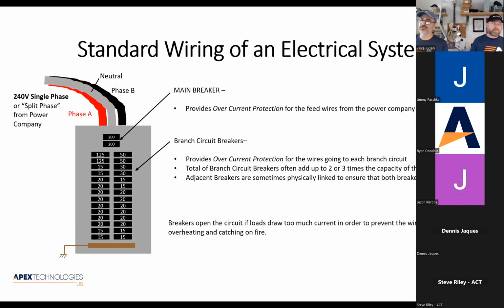So let's get back to a 240 single phase. Now, one thing I get a lot of questions on: what is single phase? What is split phase? What does that mean? For some reason, our brethren in the electrical world, the electricians of the world, even though the 240 volt is 2 phases, they still refer to that as single phase, which I understand, I'm in the biz, but I'm trying to help you guys understand it. So you'll hear me refer to it as split phase, just to remind you while we're talking that we're talking really about 2 hot phases. Both of those things mean the same thing, single phase or split phase: the 2 phases and a neutral line that are coming out of that transformer.